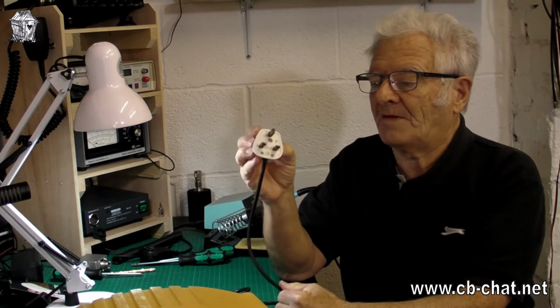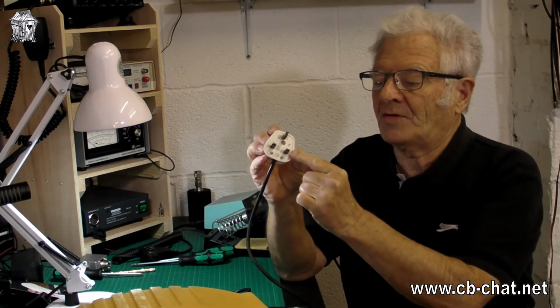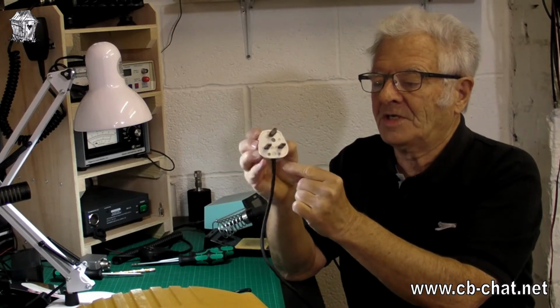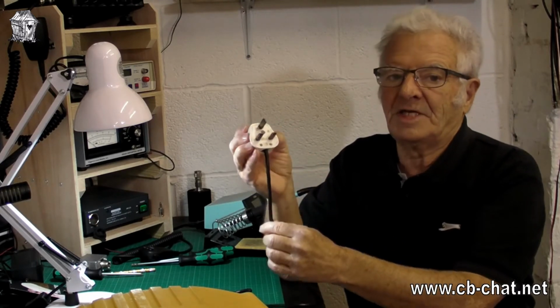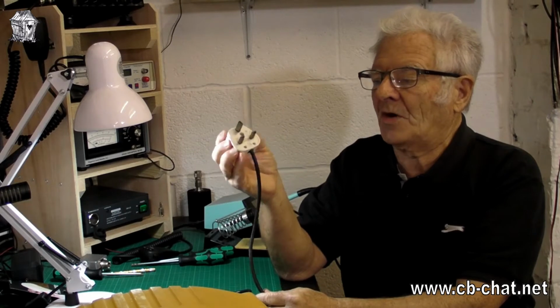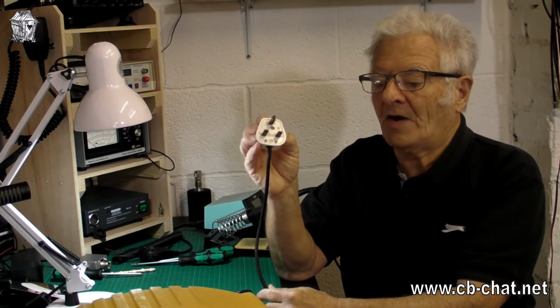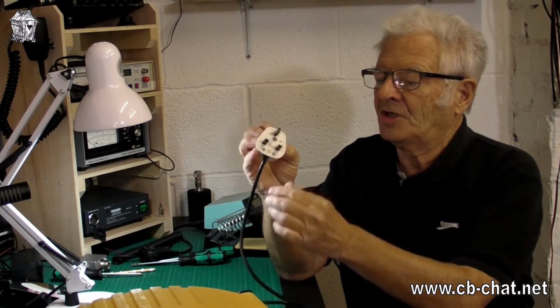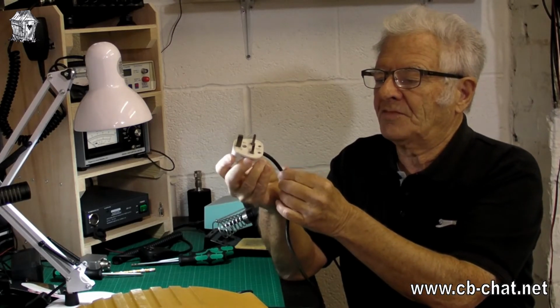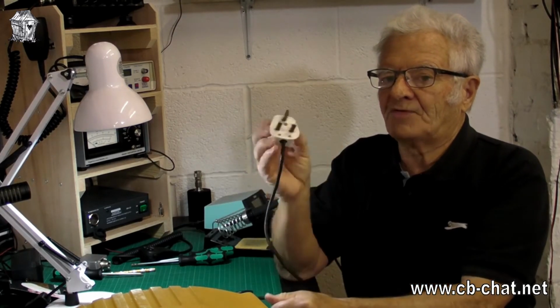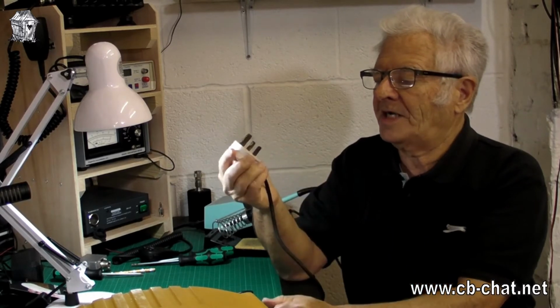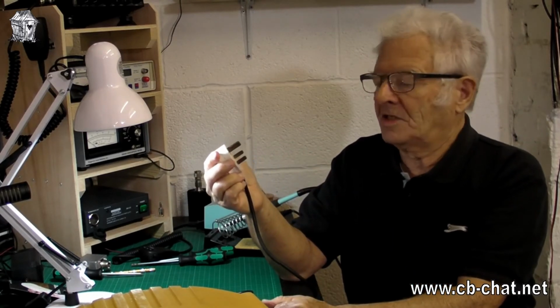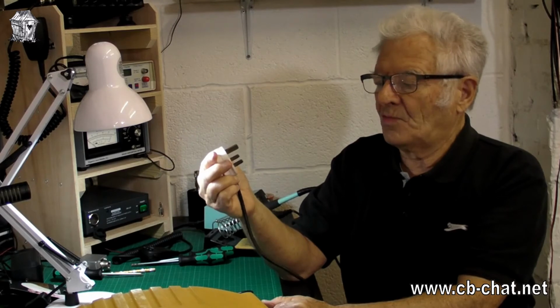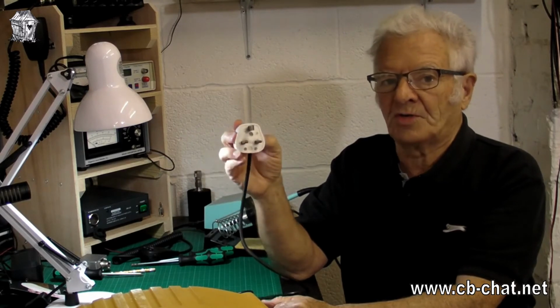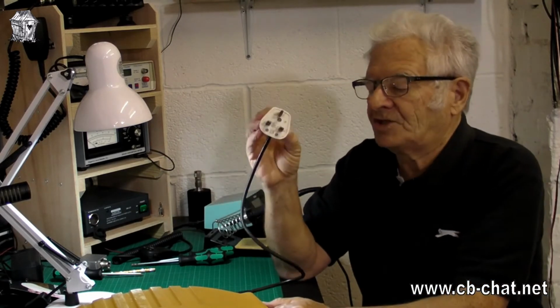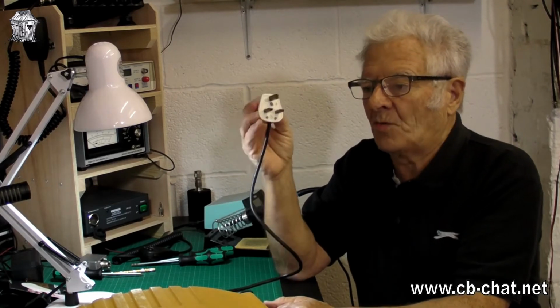Now modern 13 amp plugs have got plastic shrouding on part of them, and when this was made in the 80s, 40-50 years ago, that feature hadn't come out. They didn't have the plastic shrouding. So this one is just the brass pins. Straight away the PAT tester would look at this and say, more than my job's worth to pass this one. Well, actually, it's not a failure, it's a warning.